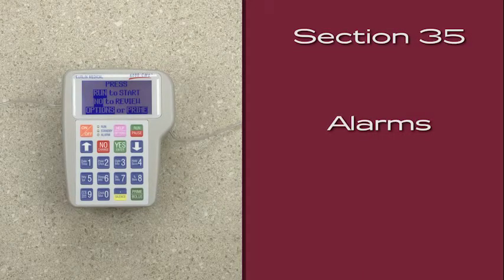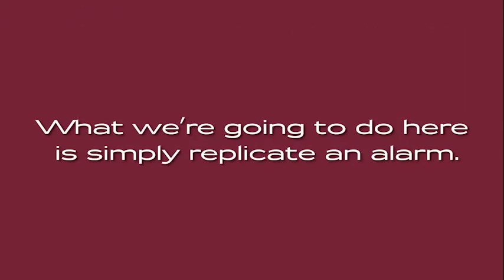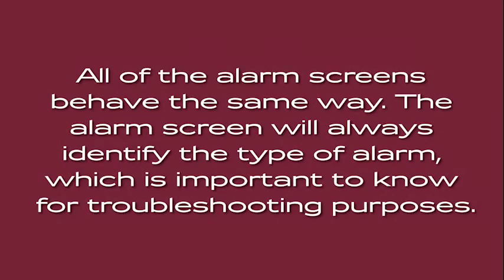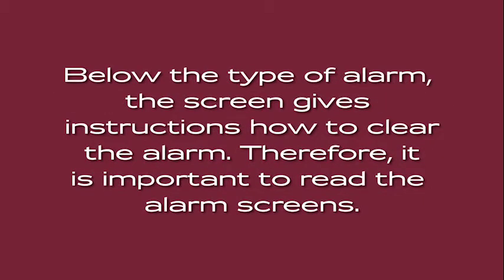Alarms. We will conclude the in-service by going over troubleshooting alarms. What we're going to do here is simply replicate an alarm. All of the alarm screens behave the same way. The alarm screen will always identify the type of alarm, which is important to know for troubleshooting purposes. Below the type of alarm, the screen gives instructions how to clear the alarm. Therefore, it is important to read the alarm screens.